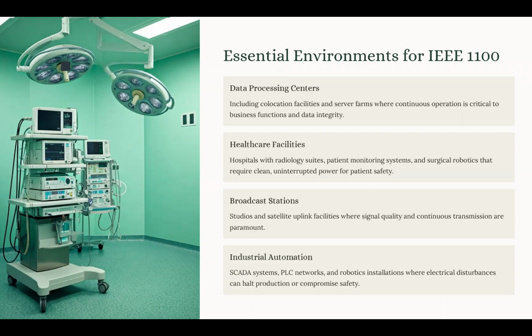These sensitive equipment exist basically everywhere, but some environments are uniquely vulnerable. Now, one would be the data processing center. IEEE 1100 is essential because continuous uptime is critical for business operation, cloud service, and data integrity. Even a millisecond power disturbance can corrupt the database or crash the servers. Also, data centers operate with high-density, sensitive electronic equipment like servers, storage arrays, and networking gear, which are highly susceptible to voltage sags, transients, and ground noise.